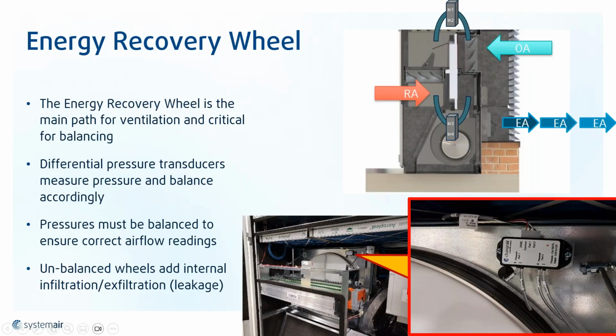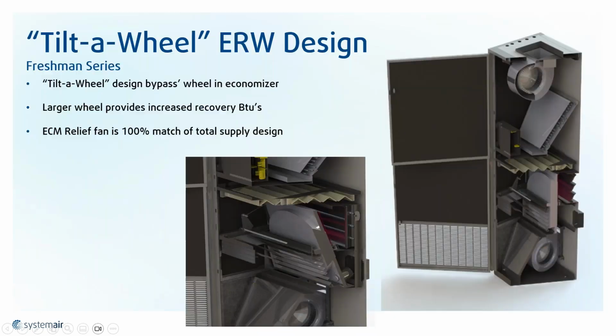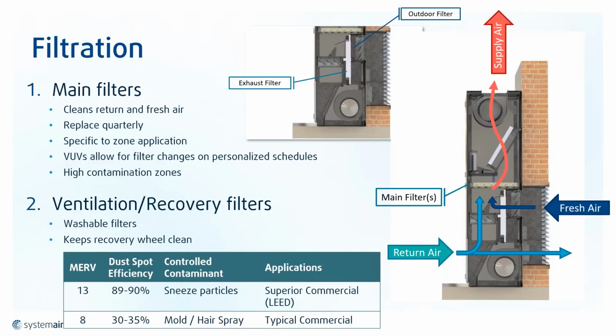One last thing I'll mention on that slide: if you have the louver and the dual air paths, we provide that divider plate, or that divider plate is necessary to separate the two air streams. We call this our tilt-a-wheel design. If you take the energy recovery wheel, it modulates the whole wheel module, will rotate or modulate and then bring the air across it to economize. So all these units, whether it's a freshman or a sophomore, can do 100% economizer based on the supply CFM. Filtration, two main filters we offer, MERV 8 and MERV 13.